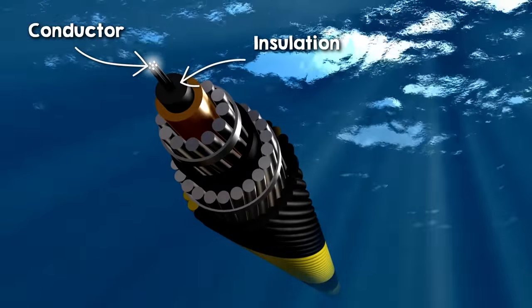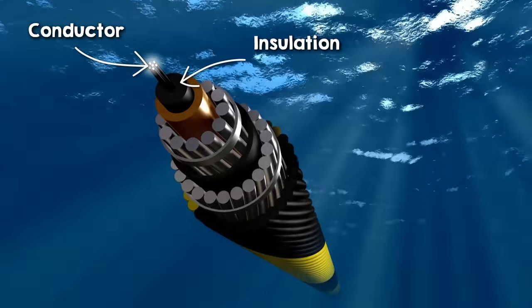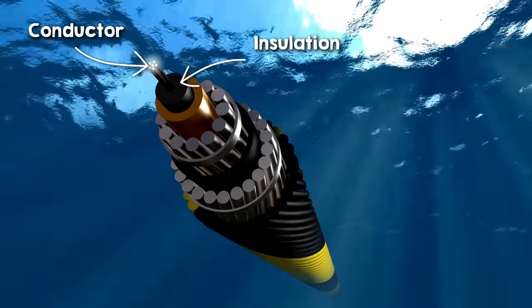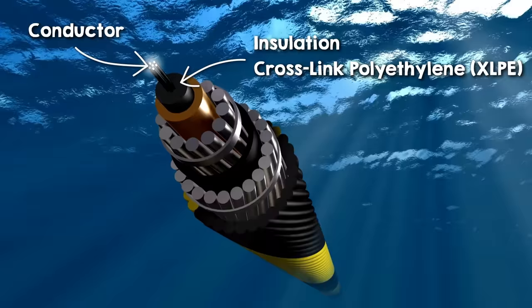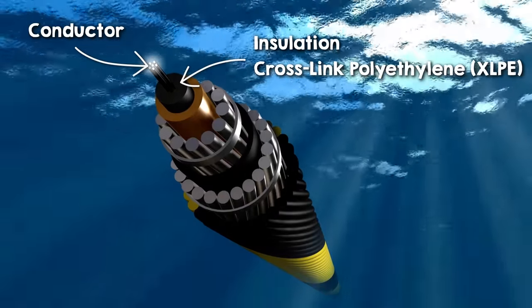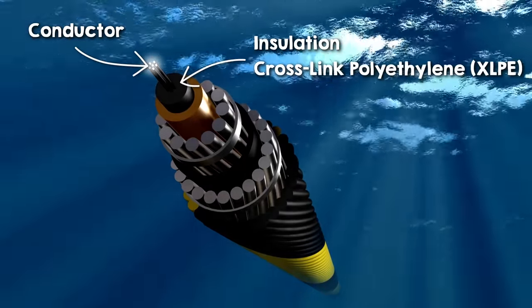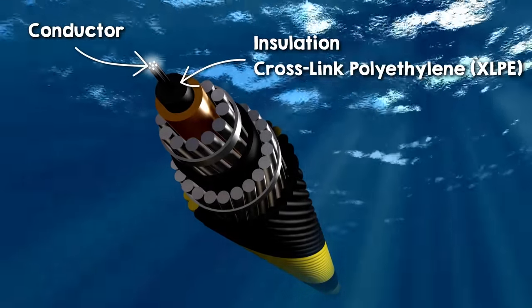There's an insulation layer surrounding the conductor, preventing electrical current from escaping to nearby conductive elements. These days, most cables use cross-linked polyethylene, XLPE, as insulation, a significant improvement over the previous norm of gas and oil impregnated cables. XLPE can withstand high electric fields in HVDC cables, offering excellent electrical and mechanical properties.